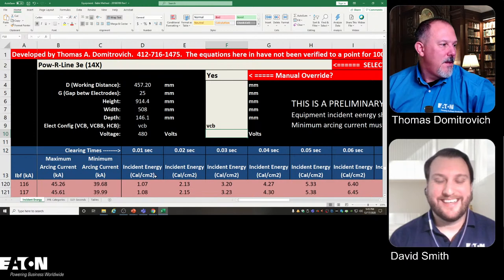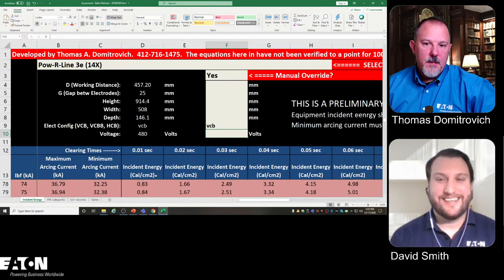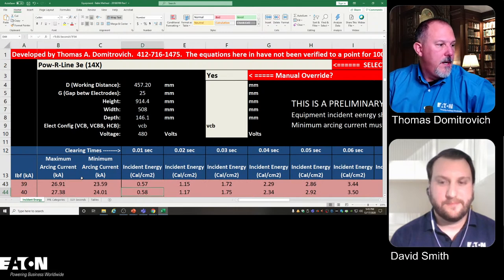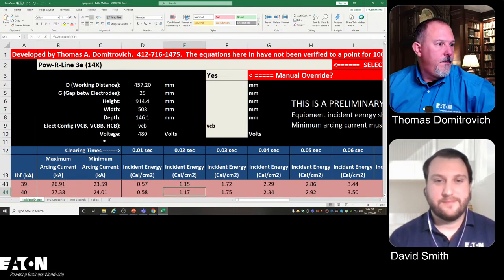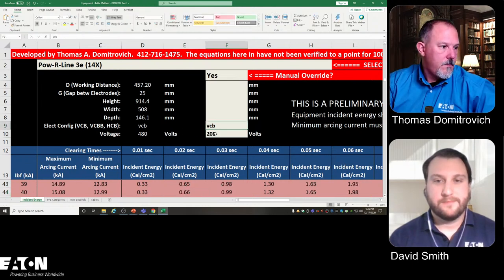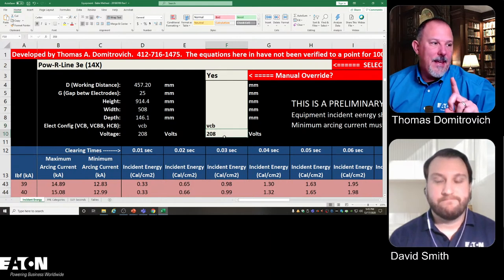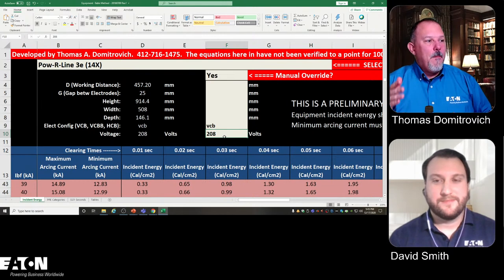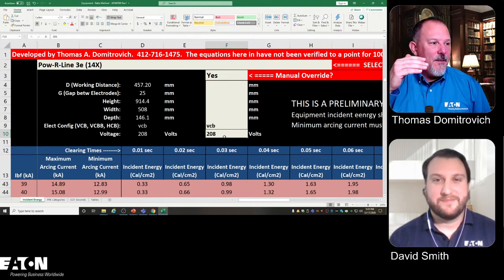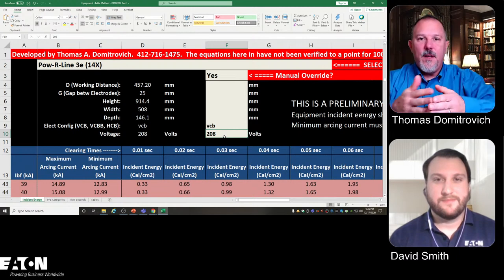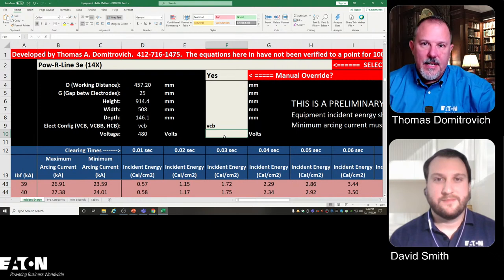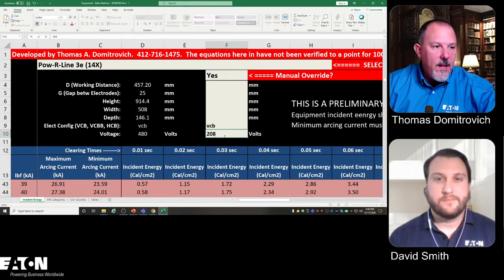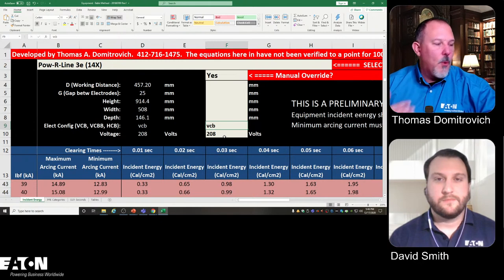All right, so if I'm at 480, and let's go back to 40,000 amps down here at the bottom. I go to 40,000 amps, 3940, I'm at 1.17 calories. If I take this down to 208, I'm at 0.66. Now, here's, and you'll say, wow, look, my clearing time and my voltage is at 208. So if I had a transformer in it and had a 480 volt secondary, and my clearing time was 0.02 seconds, I'd be at 1.17 calories. If my actual transformer was a 208 volt secondary, my incident energy would be 0.66 calories, right?